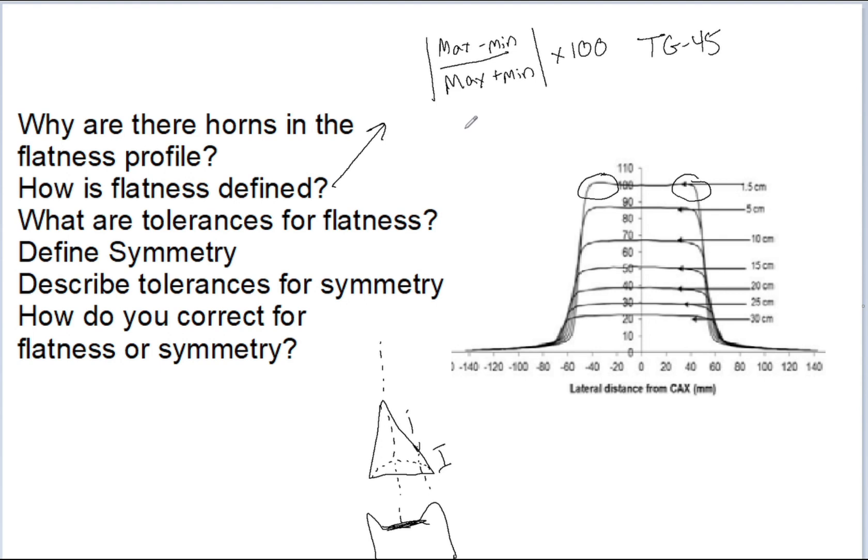What are the tolerances for flatness? TG-142 first says that you have to base your tolerances to match the treatment planning system. That is essentially your golden data and what you want your flatness and symmetry to be matched to.